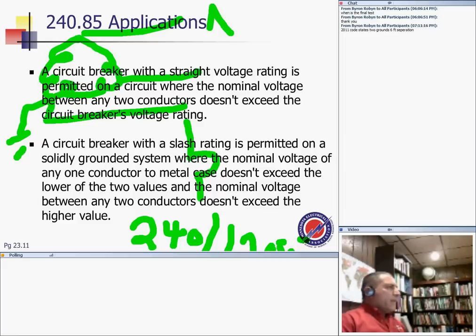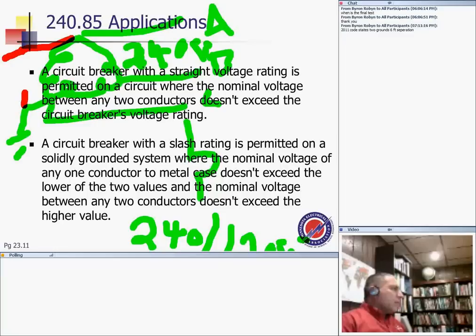Phase A, phase B, and phase C. Now, this is a 240 volt corner grounded delta. I can't install this circuit breaker on a corner grounded delta, and the reason for this is because the line to ground voltage is 240, not 120. If you take the voltage from here to the ground, it is 240, and it's higher than the 120 this circuit breaker is rated for.